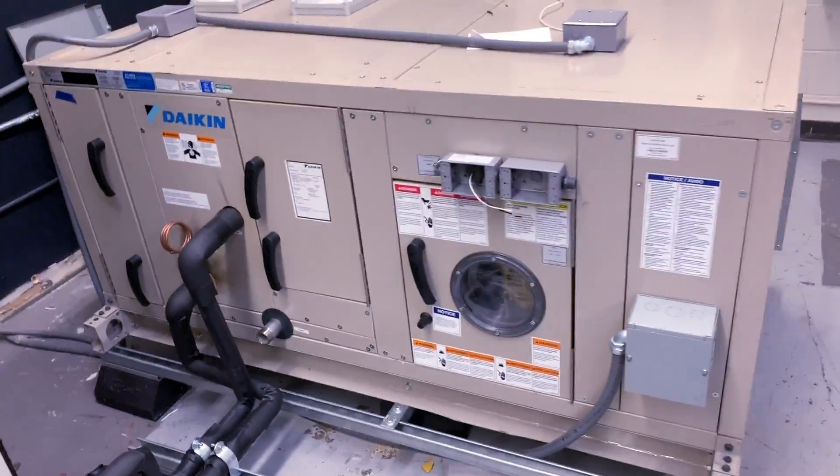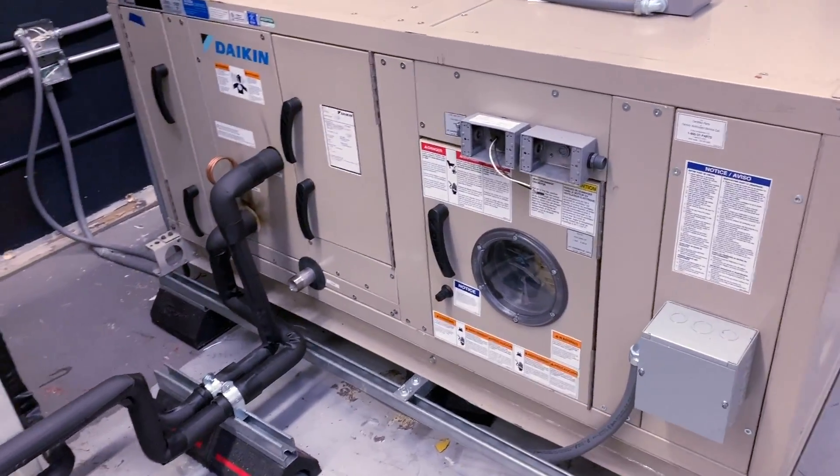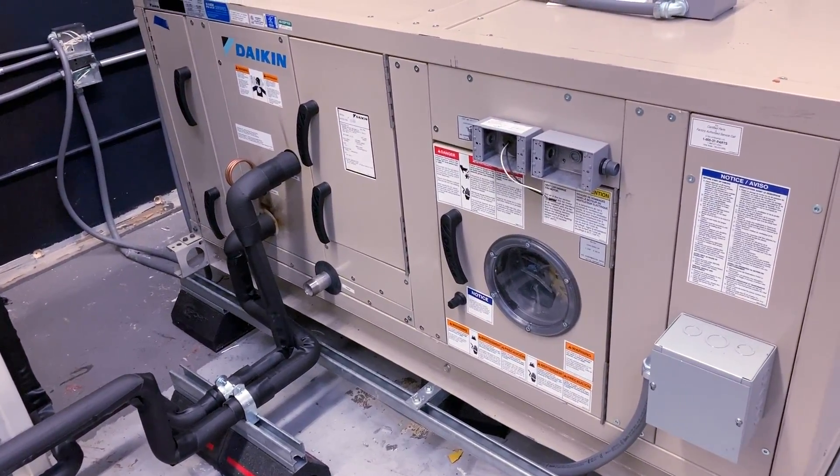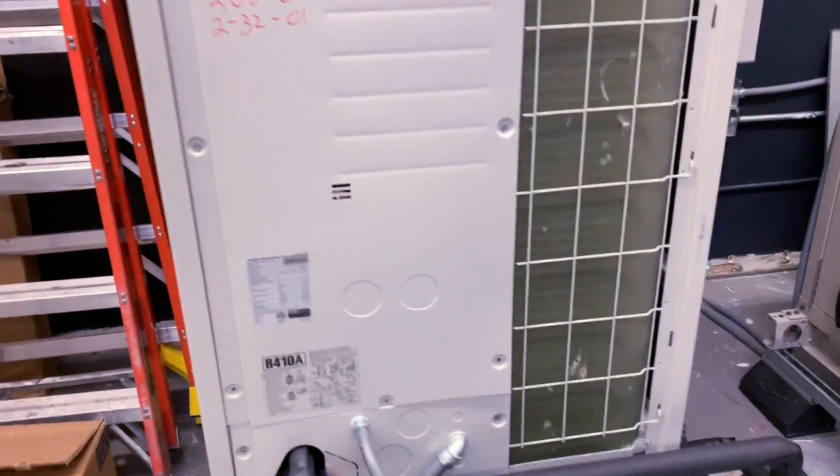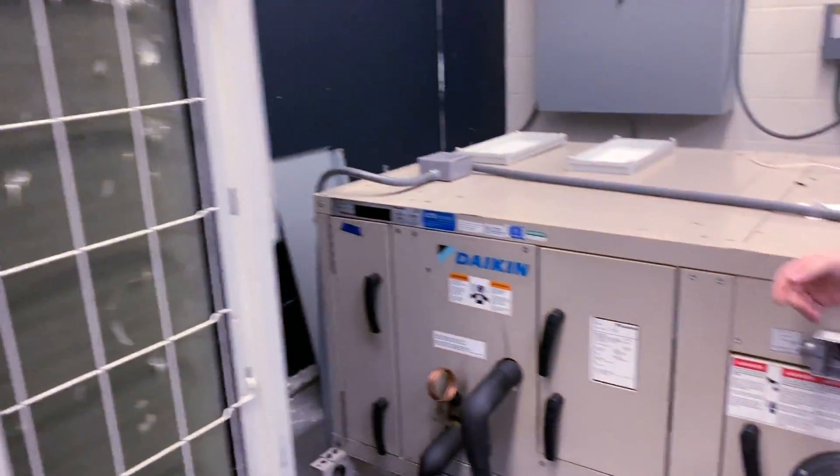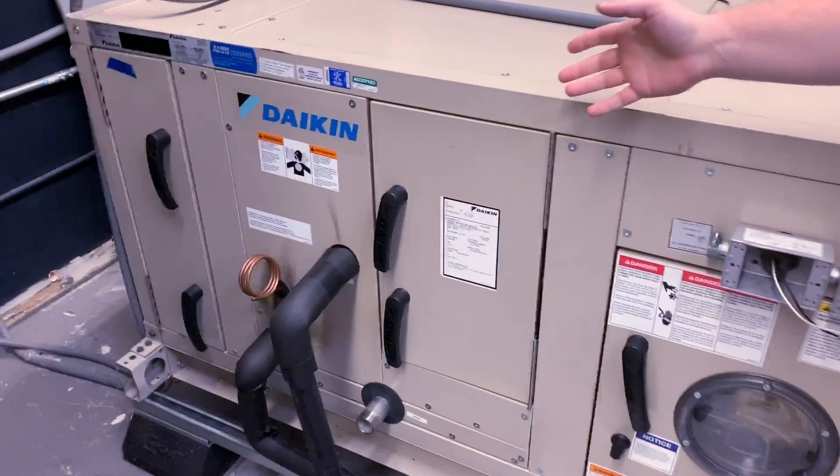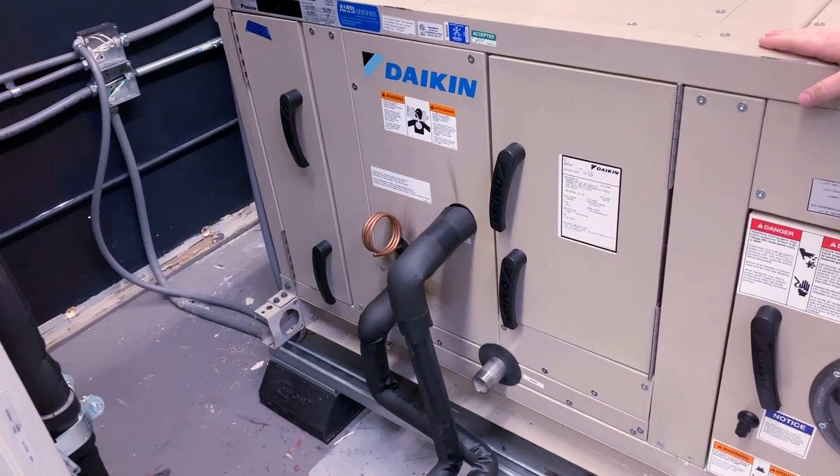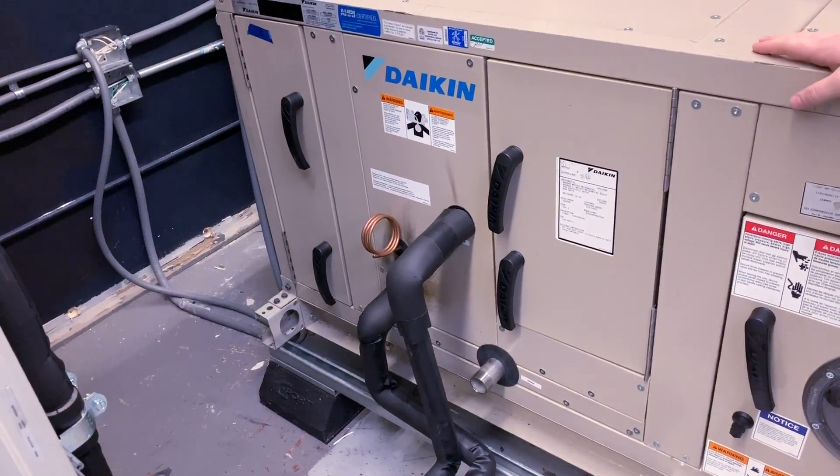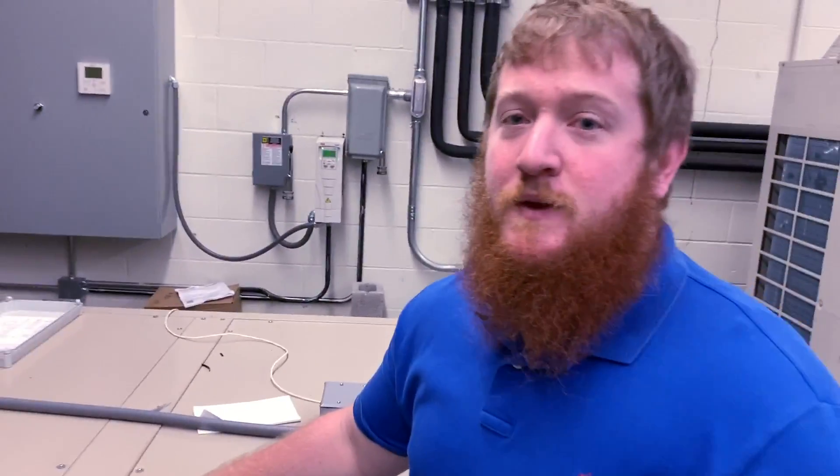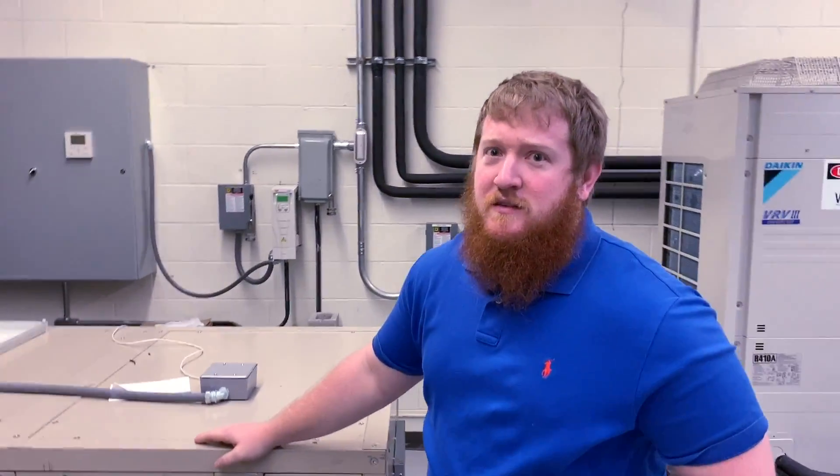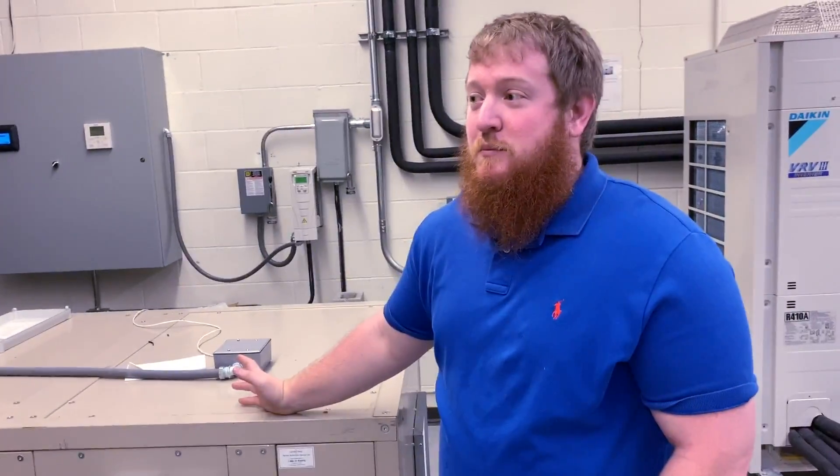It is not talking. And so then you have, this is actually interesting because I just heard about this recently. This is a project that's probably about four years old at this point. What we take is a conventional heat pump, this is our version of a heat pump, two pipe system, and you can hook up an external expansion valve to it and hook it up to an existing air handler as long as the coil meets the spec. So this is just a regular Daikin Vision air handler with a coil in it that is now a VRV air handler. I think the biggest one we did was 26 tons at 14,000 CFM, so that's a big air handler.